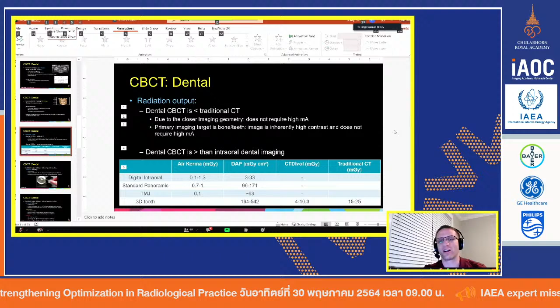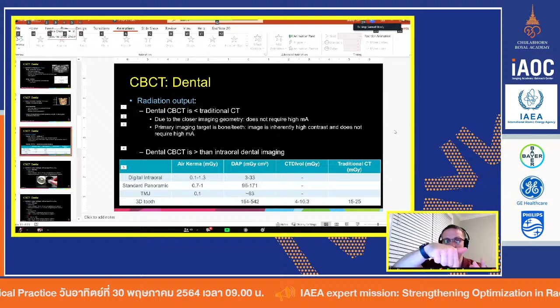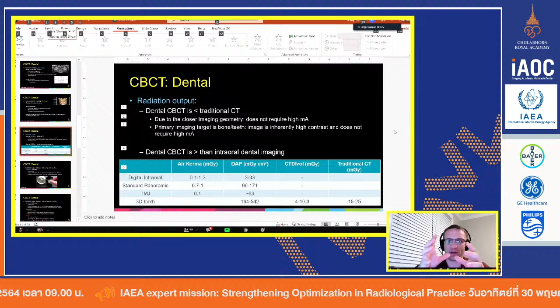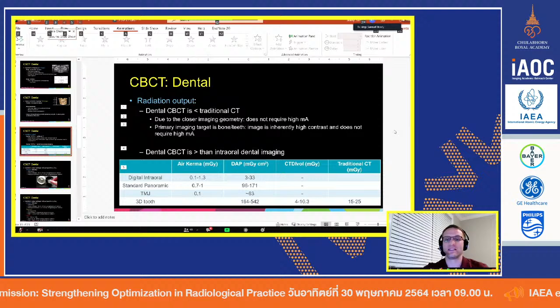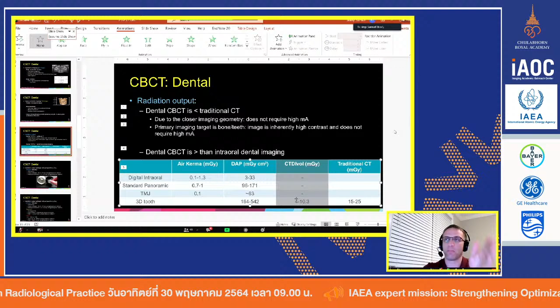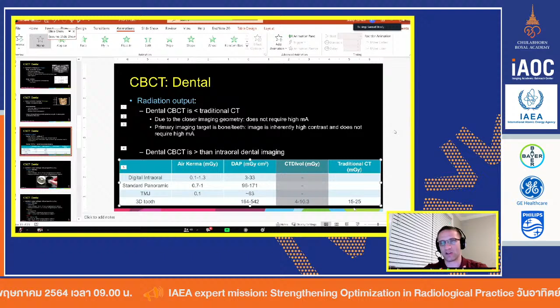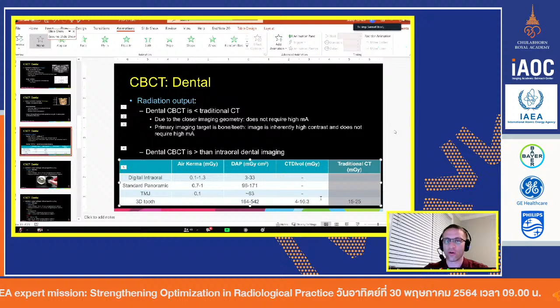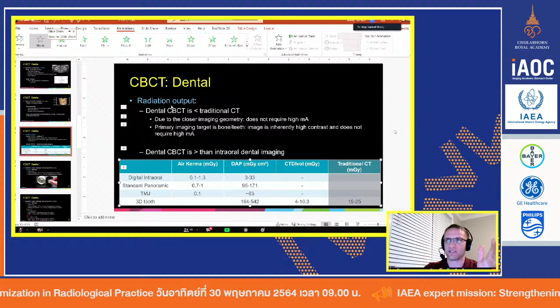We could probably talk about that for another 10 or 15 minutes. If the 10 centimeter probe is really the only tool you have, you use it and make your calculation. I don't normally compare my dental CBCT system to my traditional CT. I typically make the measurements you see right here every year, and I make sure they're the same every year. That's how I know my dental unit is performing okay. I make all these measurements on my regular CT too, and make sure those stay the same. And just know that the CBCT unit used in dentistry is typically going to be lower than regular CT.